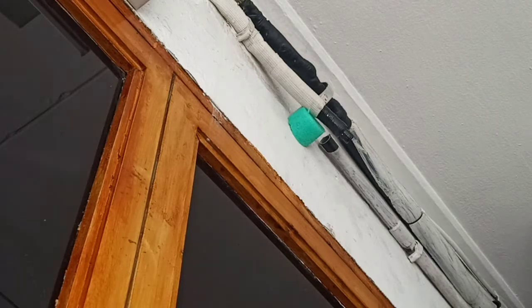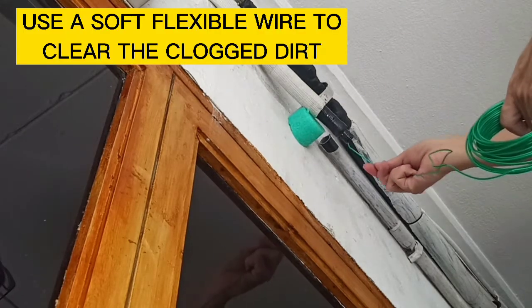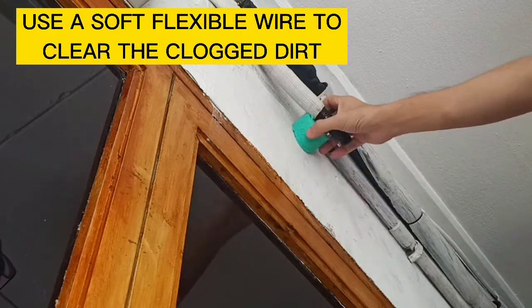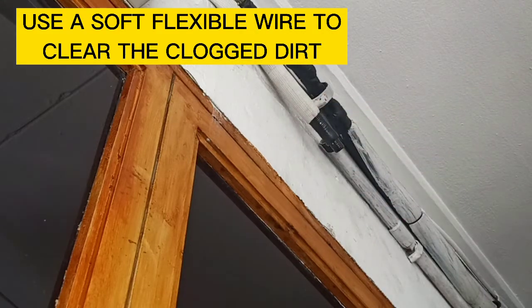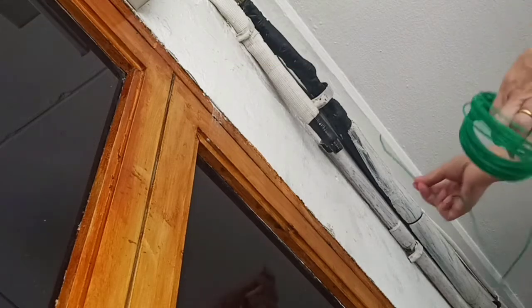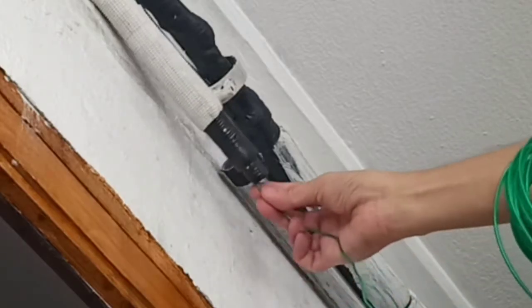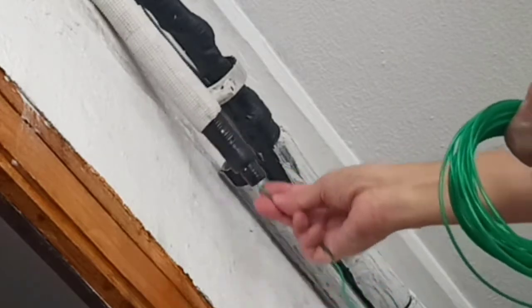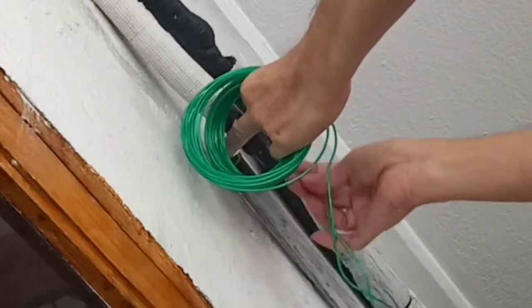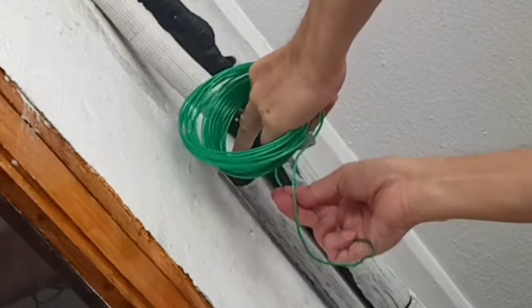As the water outlet is clogged, what you need to do is get a soft wire to put through the drain pipe and pull out all the dirt from behind. This is a soft wire which I use. It's very flexible and you can push it down the drain pipe, push it up the drain pipe and try to remove any dirt which is clogging your outlet at the back of the aircon.